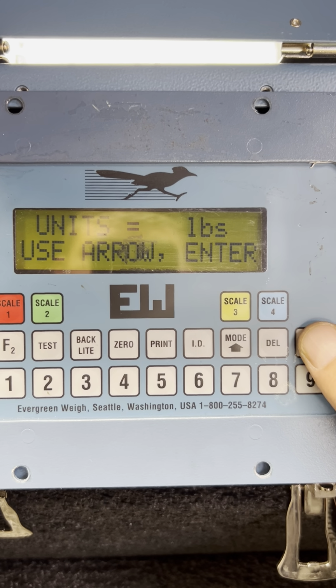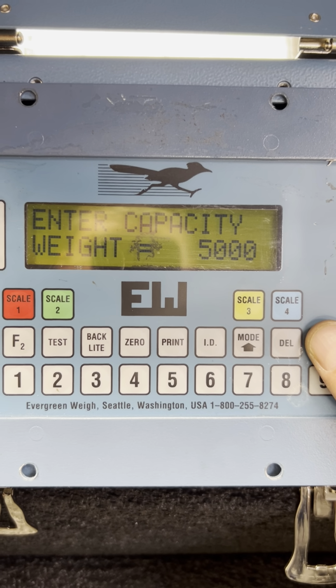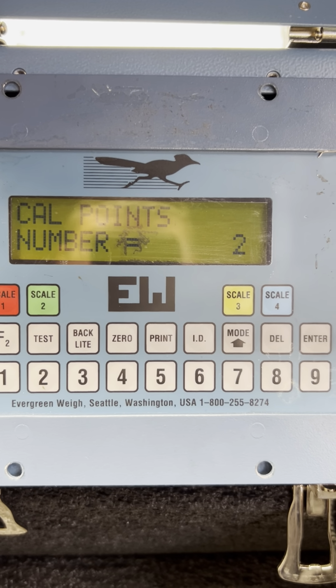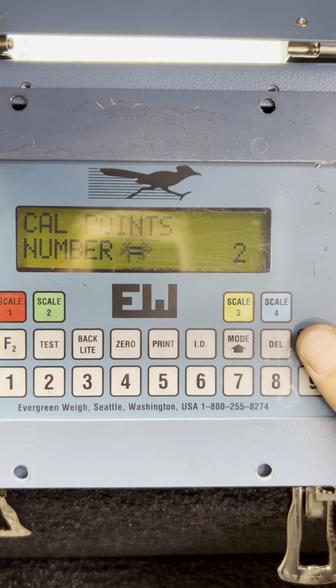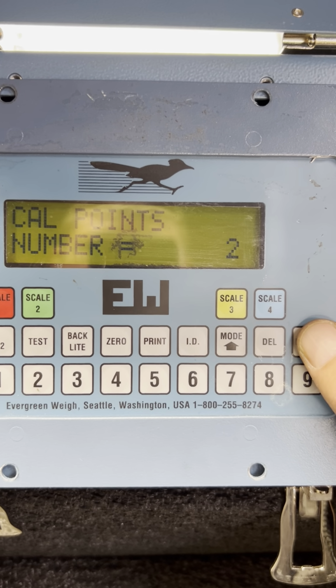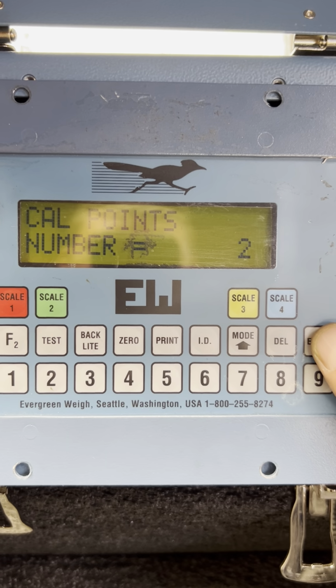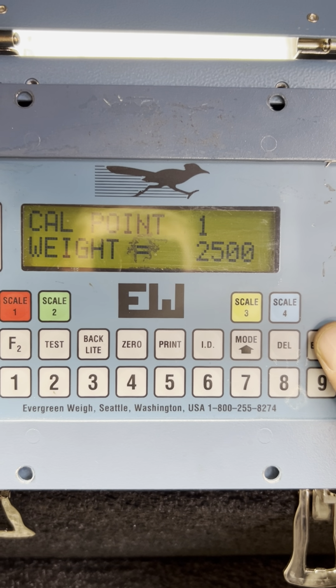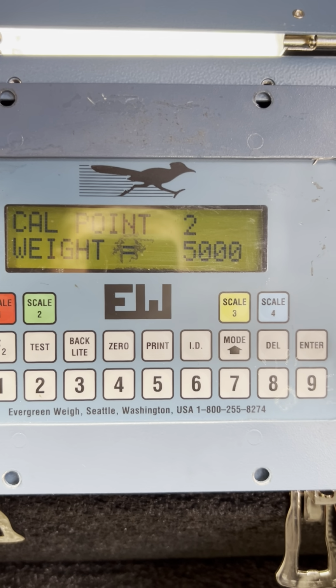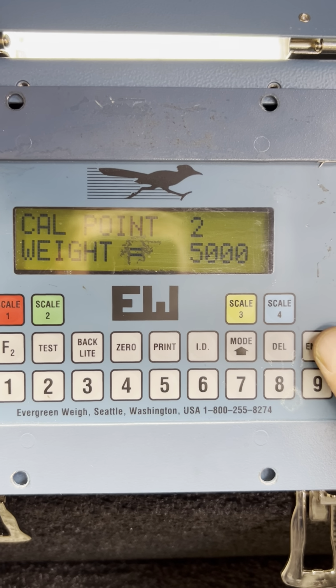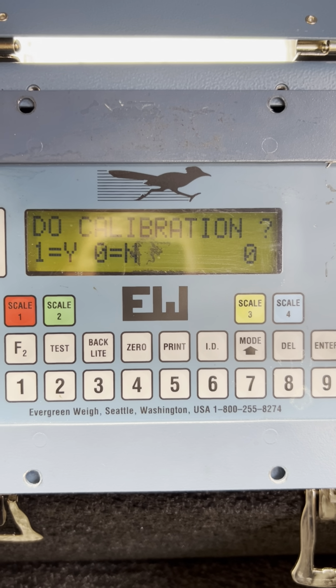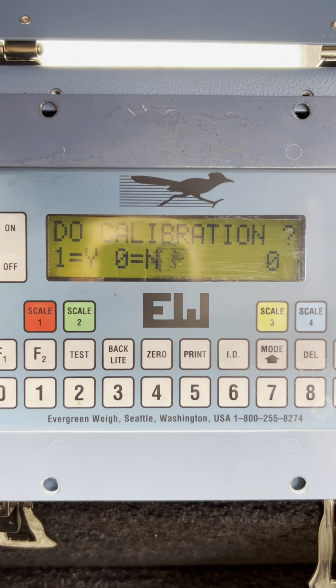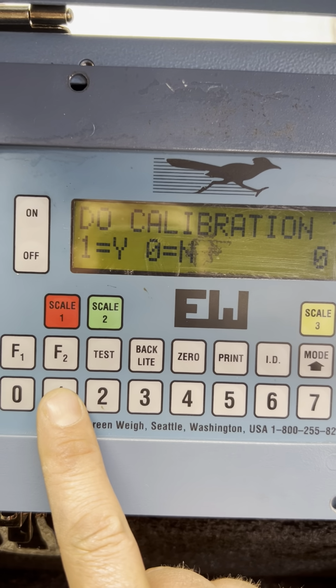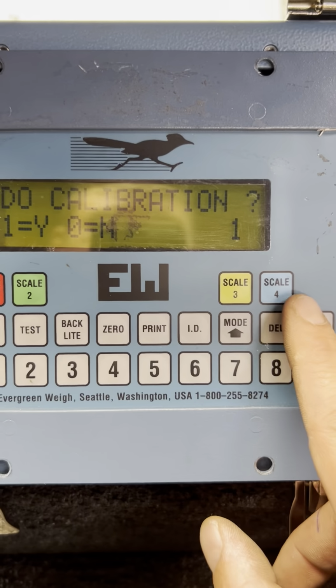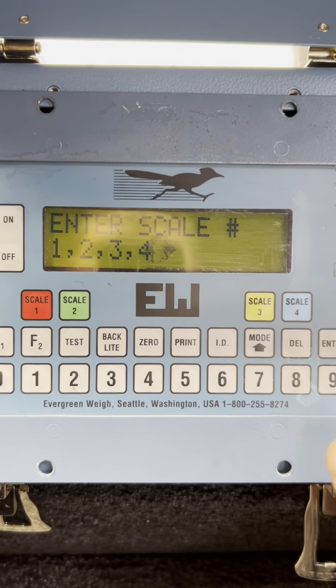Calibration units, pounds, yes. Capacity 5,000 pounds, yes. Cal points 2, okay. I agree, we will use 2 calibration points, yes. First will be 2500, okay. Another will be 5000, okay. Calibration, yes. So we press 1 and enter.